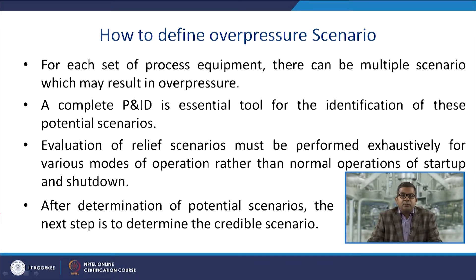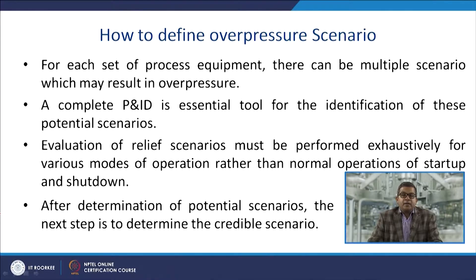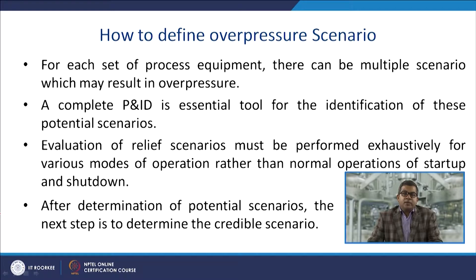For each set of process equipment there can be multiple scenarios resulting in various kinds of overpressure — sometimes due to process requirements and sometimes due to certain failures. A complete P&ID diagram is an essential tool for identifying these potential scenarios and must be evaluated exhaustively for various modes of operation, including startup and shutdown.